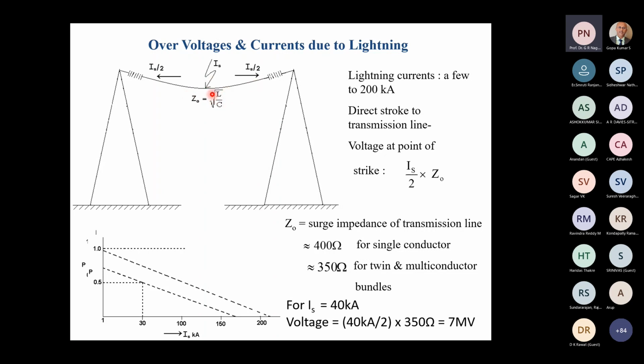So now the potential developed here is the current, 20 kiloamperes, multiplied by surge impedance. You will see here again, 40 kiloamperes becomes 20 kiloamperes. The surge impedance is 350 ohms. It becomes 7 megavolts directly on the phase conductor. So if you allow it like this, it will go and hit the transformer. The transformer will be destroyed in practically no time. Therefore, we have to design this insulator string very, very carefully. Remember, this design is very, very critical. If this flashes over, the voltage across the line to ground gets limited by this value. We'll come to this once again later.